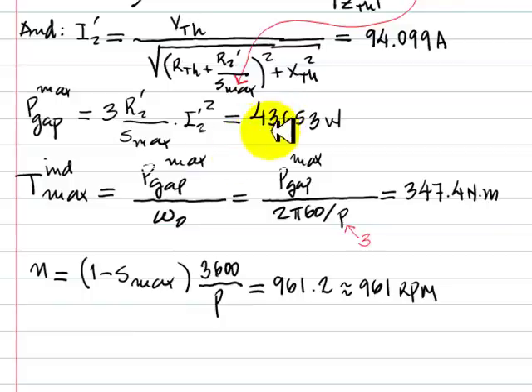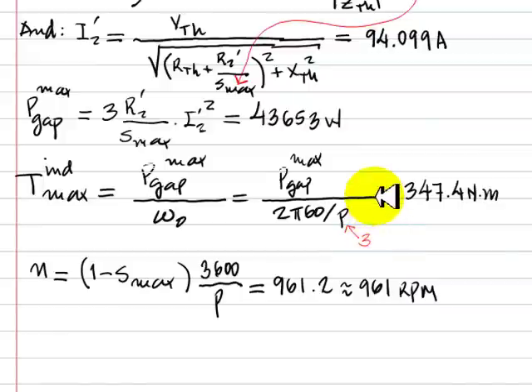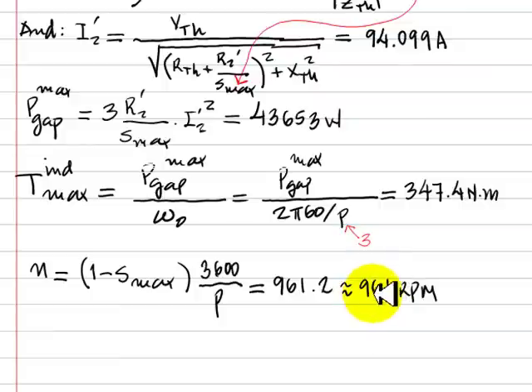To find that torque, we divide the gap power by omega naught. Omega naught is 2π times the frequency (60 Hz) divided by the number of pole pairs — we have 6 poles, so p = 3. That tells us the maximum torque is 347 Nm. The velocity at that maximum torque slip is (1 − s) times the synchronous velocity, which is 3600 divided by p, giving 961 RPM. That takes care of part A.